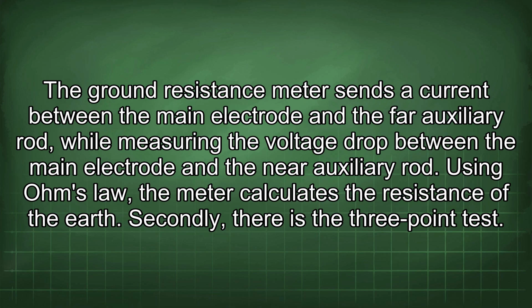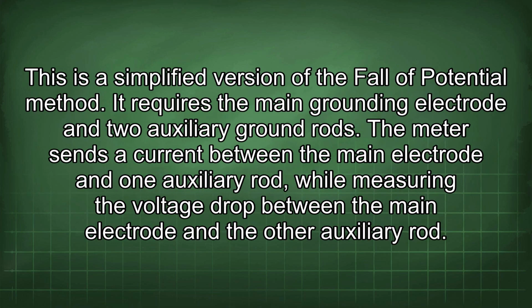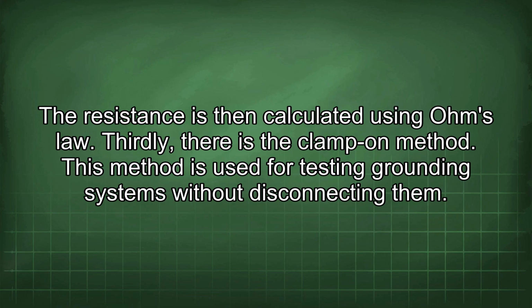Using Ohm's law, the meter calculates the resistance of the earth. Secondly, there is the three-point test. This is a simplified version of the Fall of Potential method. It requires the main grounding electrode and two auxiliary ground rods. The meter sends a current between the main electrode and one auxiliary rod, while measuring the voltage drop between the main electrode and the other auxiliary rod. The resistance is then calculated using Ohm's law.